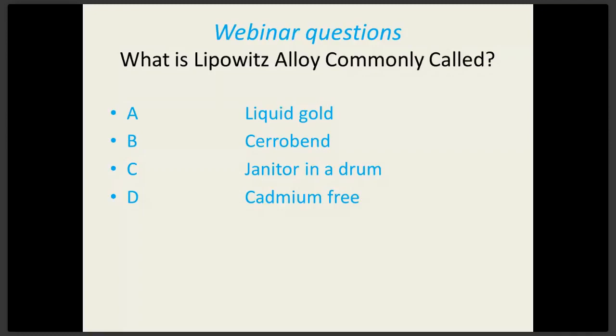That answer is Cerrobend. Cerrobend is a eutectic alloy. You can impress people at a cocktail party by throwing out that word. The components of Cerrobend are lead, tin, cadmium, and bismuth. Together, they make an alloy that melts at a very low temperature, way lower than the melting point of any of the constituents of the alloy. So it's a eutectic alloy. The hazardous material in Cerrobend is cadmium, which is a carcinogen, and lead, which is a neurotoxin. Cadmium and lead are the two culprits in Cerrobend that make it bad for you.